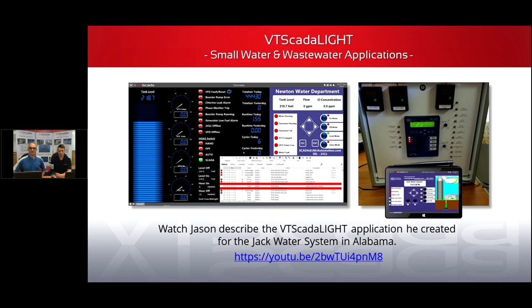The very first decision we had to make was what HMI to go with. So having worked with so many, but Survalent being the one that is in the current utility I work for, we went to Survalent first. The only thing Survalent could offer is their lowest package is 7,500 tags. And, I won't name pricing, but it's very expensive. And that does not come with a historian. That does not come with alarming. And it's not practical, especially for small and mid-sized systems. So then I thought about FactoryTalk, and I've used Rockwell for quite a bit, and I don't like having to use WIN-911 or third-party applications, and honestly, Rockwell tends to be kind of proprietary, and we wanted a more open source solution.